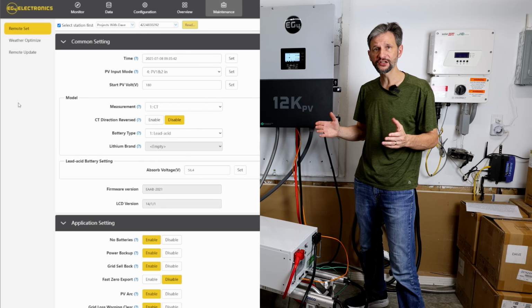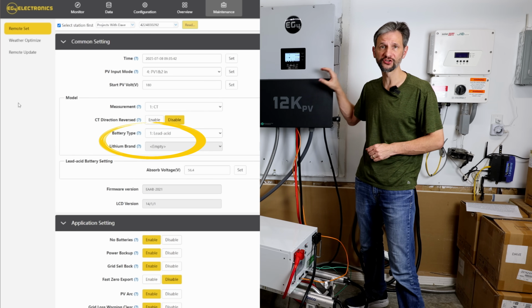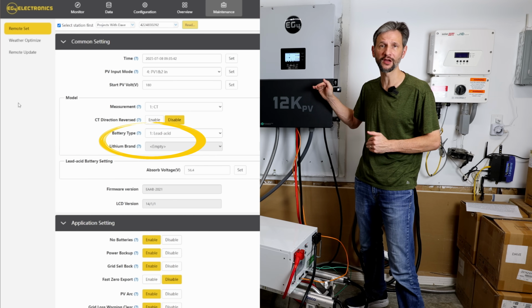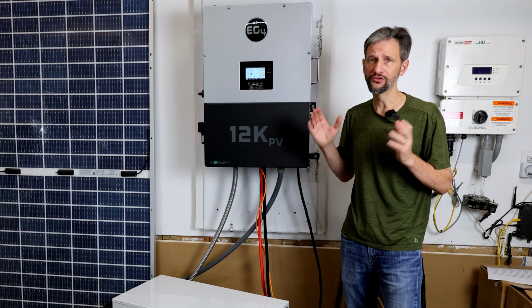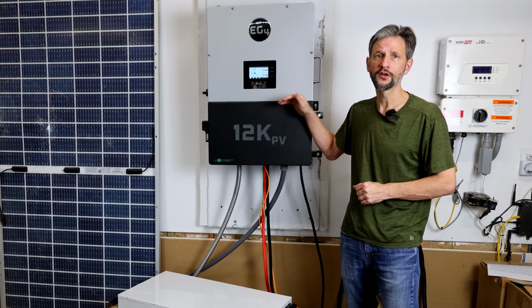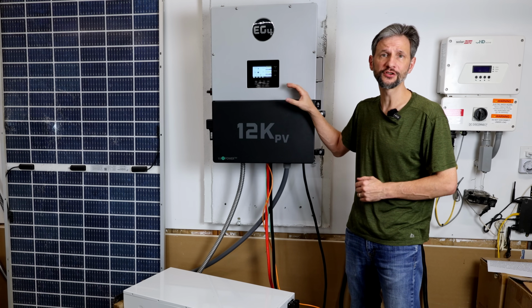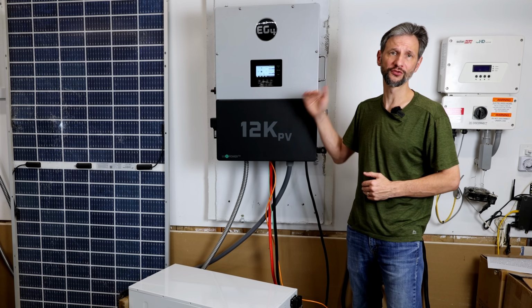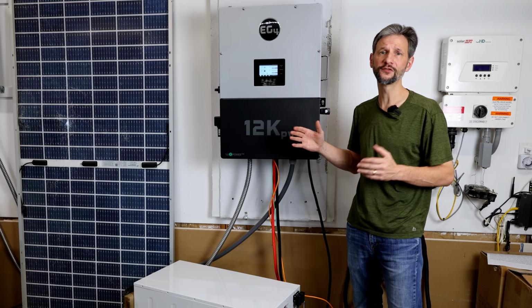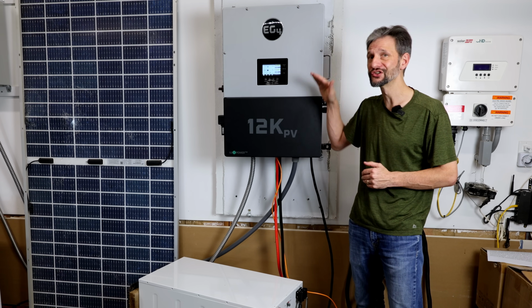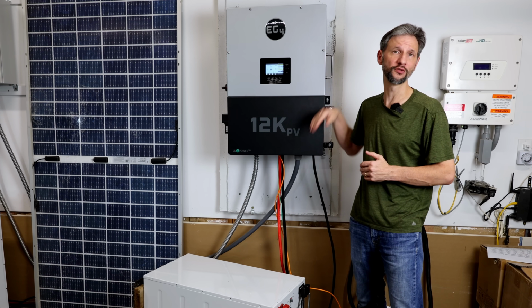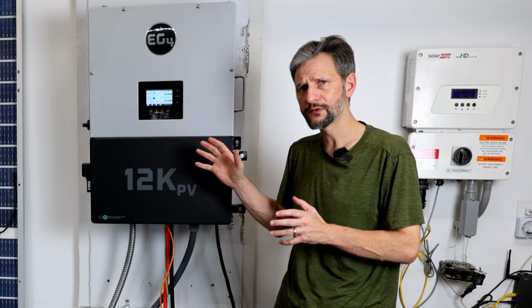If you don't want communication, you can select the user mode, which is called lead acid, and just control everything by voltage, which I like to do anyway. You can combine communication for visibility of the state of charge and still use voltage to control the charging. And that can actually give you a little bit more control, since state of charge can drift over time if you don't charge it to 100% on a regular basis. So let's review those settings.